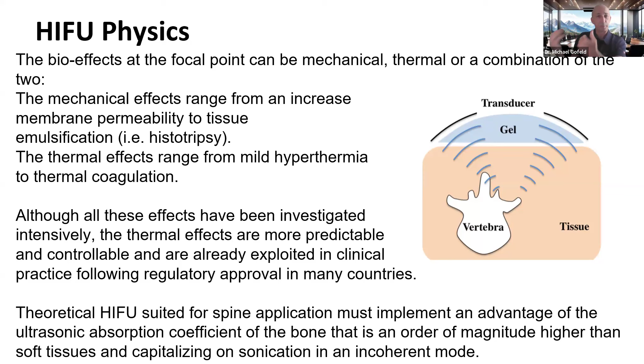So what is incoherent mode? If you think about the emitter of HIFU, it's several rings, multiple rings, and every ring will emit the same frequency or the same energy, but it can be emitted at the same time, or at different times. If it's emitted at different times, those ring signals will confuse each other and will not create a lesion. They will create a zone that we call the therapeutic zone, about 5 centimeters. In this 5 centimeter zone, the lesion will be created only if the beam meets bone tissue, and by meeting bone tissue, it will be absorbed, creating a lesion.